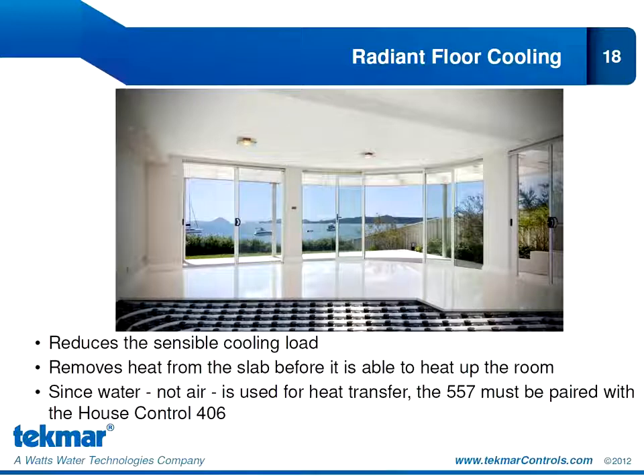So radiant floor cooling is especially effective in areas where solar gain can be up to 80% of the load. And how it does that is it removes heat from the slab before it's able to heat up the room. So I like to think of it as a proactive approach to cooling instead of a reactive approach. Now, since we're using water to distribute this energy, we need to pair the 557 with the 406 house control.